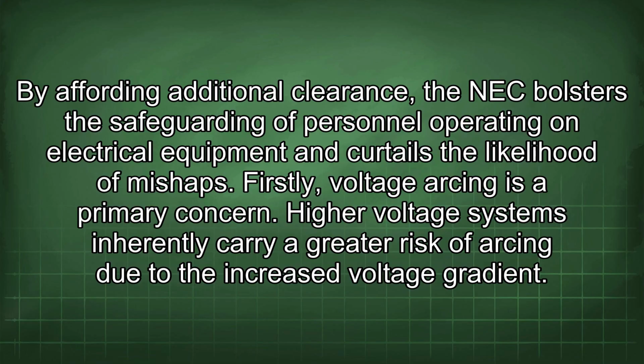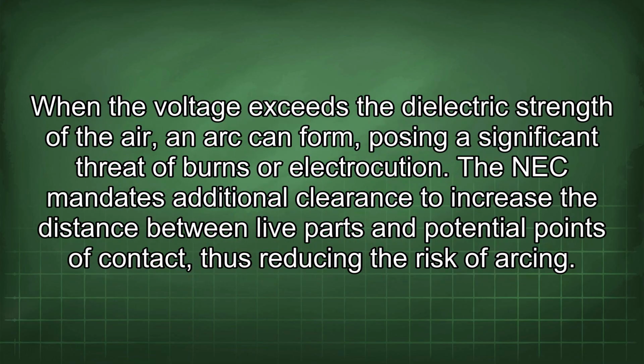Firstly, voltage arcing is a primary concern. Higher voltage systems inherently carry a greater risk of arcing due to the increased voltage gradient. When the voltage exceeds the dielectric strength of the air, an arc can form, posing a significant threat of burns or electrocution. The NEC mandates additional clearance to increase the distance between live parts and potential points of contact, thus reducing the risk of arcing.